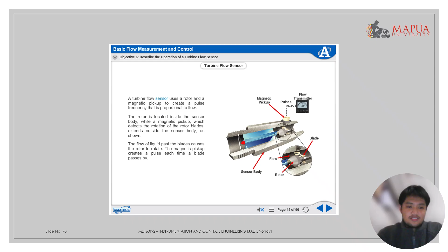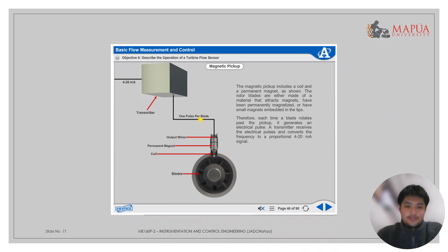The magnetic pickup includes a coil and a permanent magnet as shown. The rotor blades are either made of a material that attracts magnets, have been permanently magnetized, or have small magnets embedded in the tips. Therefore, each time a blade rotates past the pickup, it generates an electric pulse. The transmitter receives the electrical pulses and converts the frequency to a proportional 4 to 20 milliamp signal.